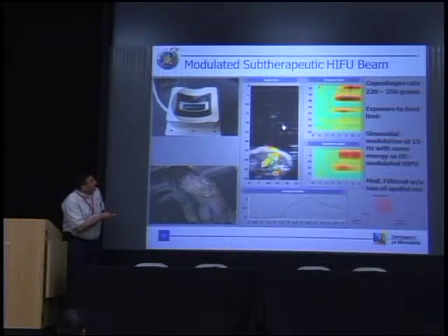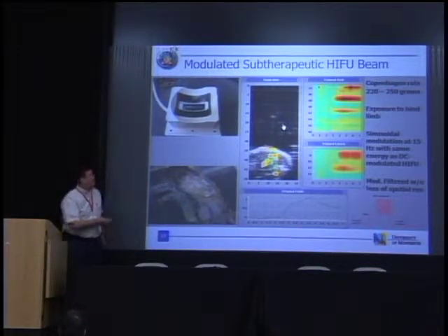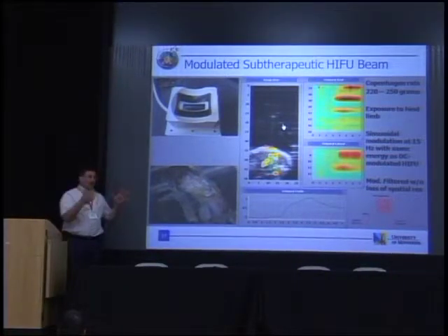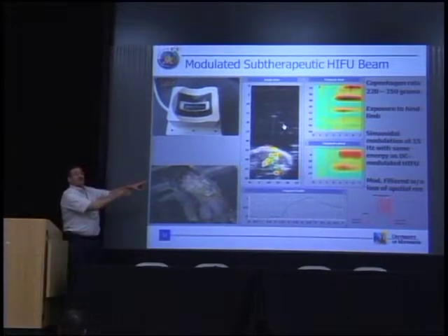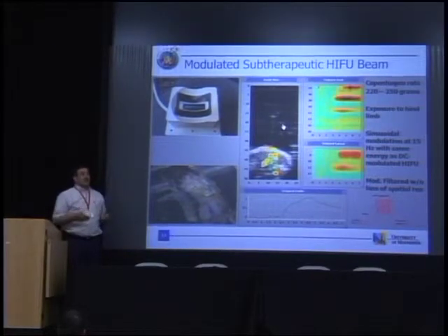And so what you're seeing is a lot of artifacts. So this is actually prefocal heating. This is actual heating. Okay. And here there's a blood vessel. I see. Yeah, and this is a boundary effect at the edge of the data. So I can tell you every one of these what kind of artifact it is. We have not really shown this nice clean heating pattern. There are artifacts, not heat. This is actual heating. This is artifact. Gotcha. Yeah, but it's known, where it's actually pulsating blood. We can see the pulsation, the blood vessel, and so on. So if I had the time, I would explain every aspect of this image. I can tell you where it's coming from. So we know. Now it's a matter of algorithmically starting to deal with these things.